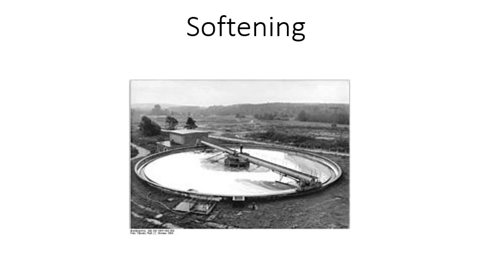It's done by adding lime to the water, which converts carbon dioxide first. CO2 does not need to be removed, but it consumes some of the lime. The pH is raised to 8.3. So CO2 plus Ca(OH)2 becomes CaCO3, which precipitates, and water.